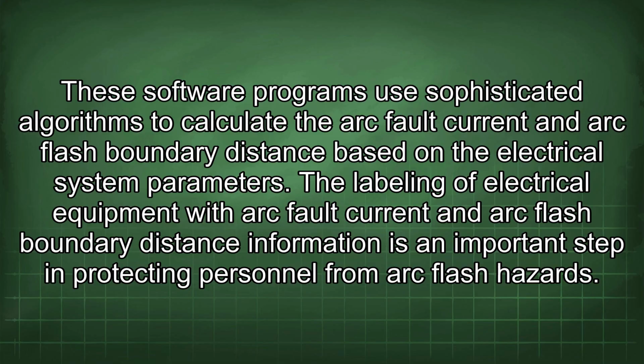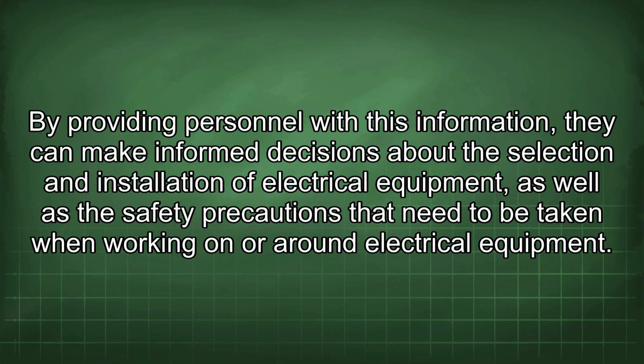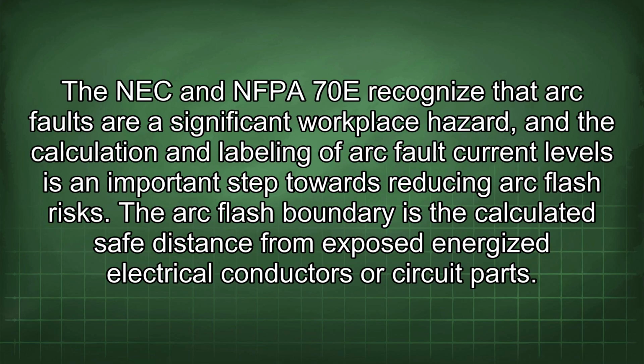The labeling of electrical equipment with arc fault current and arc flash boundary distance information is an important step in protecting personnel from arc flash hazards. By providing personnel with this information, they can make informed decisions about the selection and installation of electrical equipment, as well as the safety precautions that need to be taken when working on or around electrical equipment. The NEC and NFPA 70E recognize that arc faults are a significant workplace hazard, and the calculation and labeling of arc fault current levels is an important step towards reducing arc flash risks.